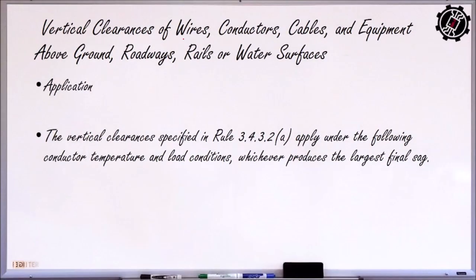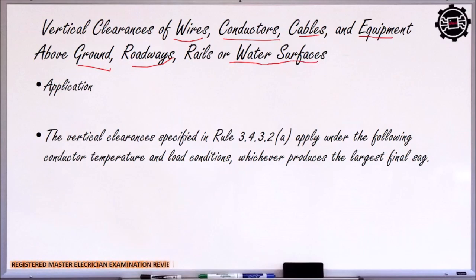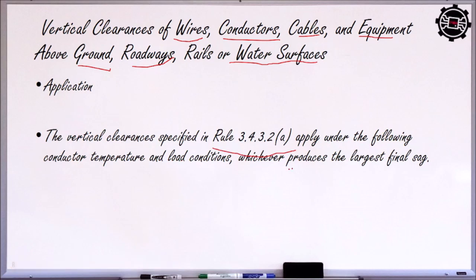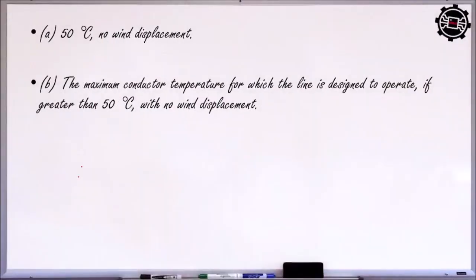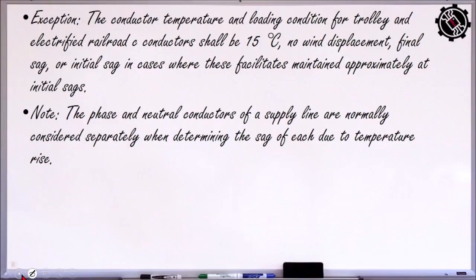Okay, so vertical clearance of wires, conductors, cables, equipment above ground, roadways, rails, or water surfaces. So the vertical clearance specified on this rule shall apply under the following conductor temperature and load conditions, whichever produces the largest final sag. Okay. So 50 degrees Celsius, tapos walang wind displacement. Pwede din the maximum temperature of the conductor operate if greater than 50 with no wind displacement. Yan yung i-consider as the sag.